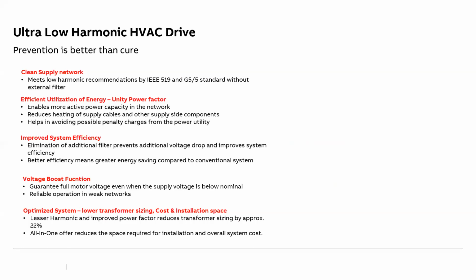Mostly the chiller manufacturers have now shifted to this active front end technology, and now even for smaller loads, people have started considering this, especially in rural applications where even a slight harmonic is not desired in the network. So there people are going with this technology.